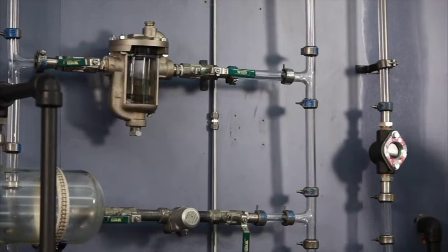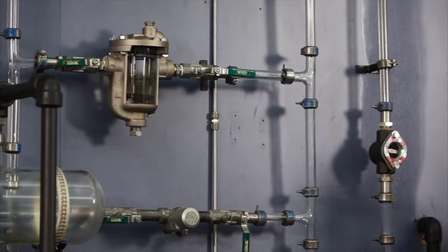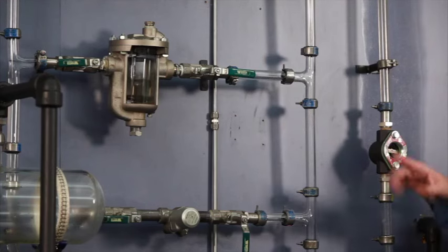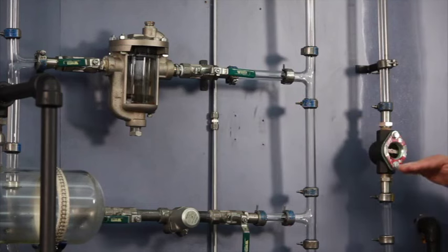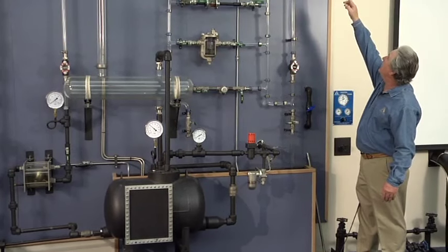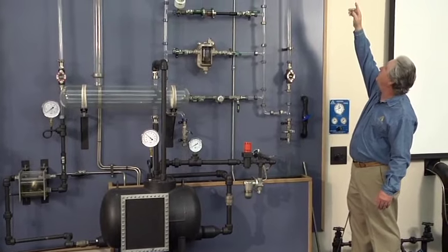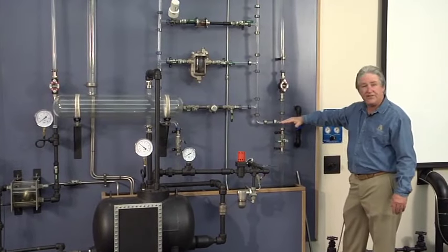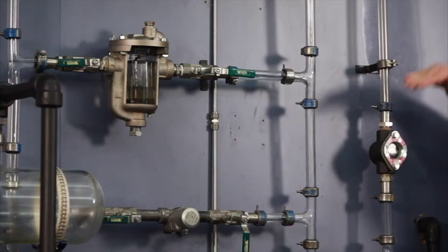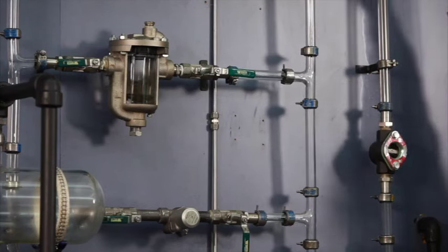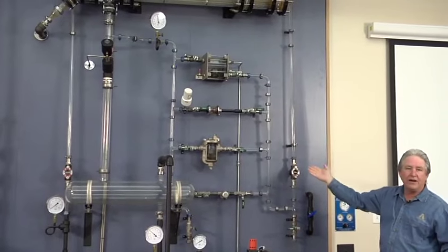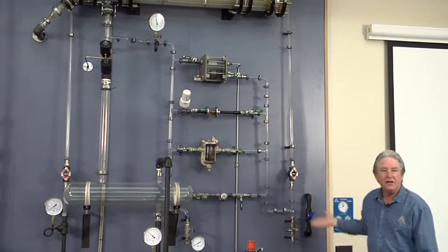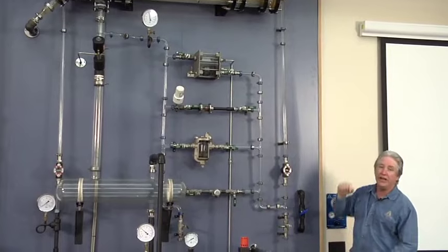Right now, what we've just done by valving in the condensate header is we're slowly inducing back pressure on the trap. We're inducing the back pressure by allowing the liquid head to generate. Look at the level now. The level is almost to the top, but remember, 1 psi for every 2 feet. There's a foot, there's a foot, there's a foot, there's a foot. So we're slowly cutting back on the differential across this trap by generating that amount of liquid head.